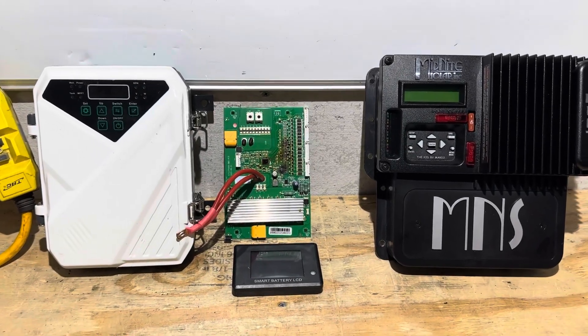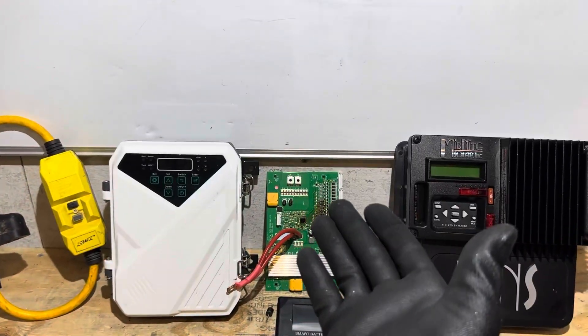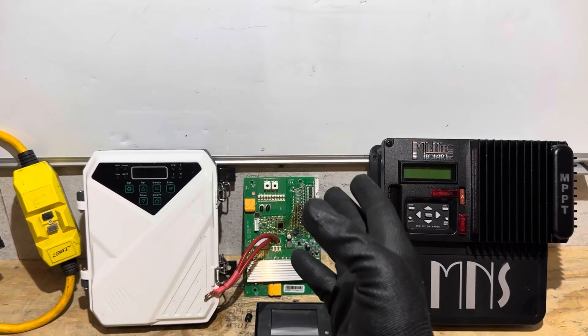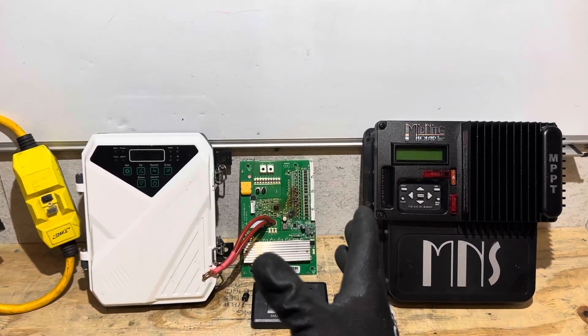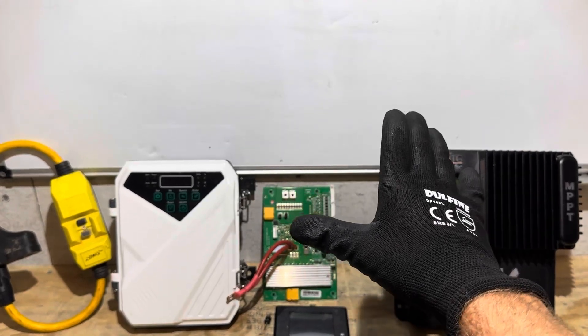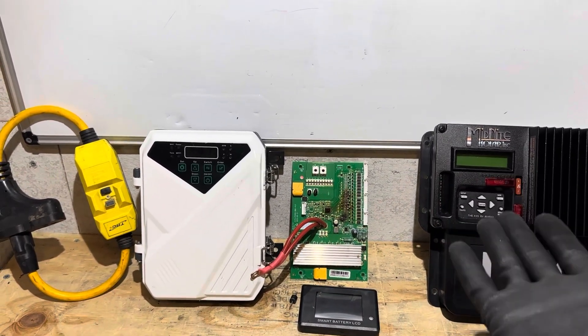There was a DC overcurrent fault on the inverter. Once it comes back up, it's still missing some batteries — only some batteries are on, some are still off. But how did that happen? I had all the PV switches off. I even had the inverter PV input switched off — that's two layers of switches it would have had to jump over. I don't think it came in that way. I've got line filters on everything, surge protection on the batteries themselves. From what I observed, the actual closest the bolt came was to a different array — about 150 feet away from where the inverter is. So let me show you some other stuff that happened to components that weren't even connected to anything, to show you how strong that lightning was.